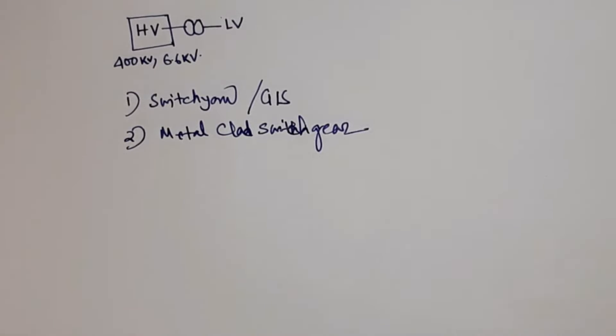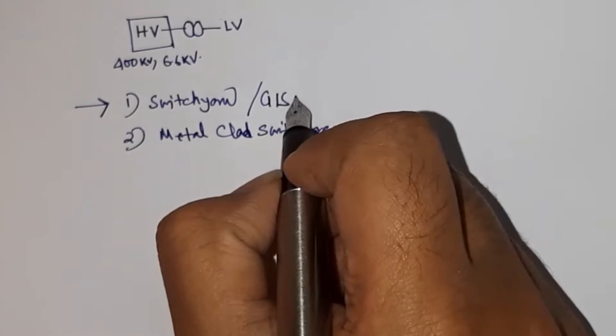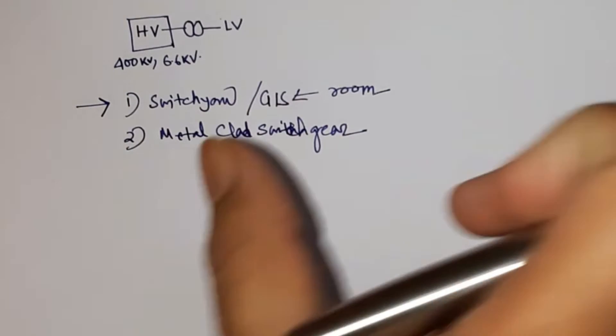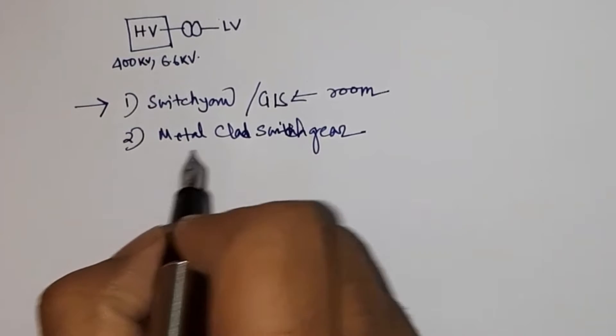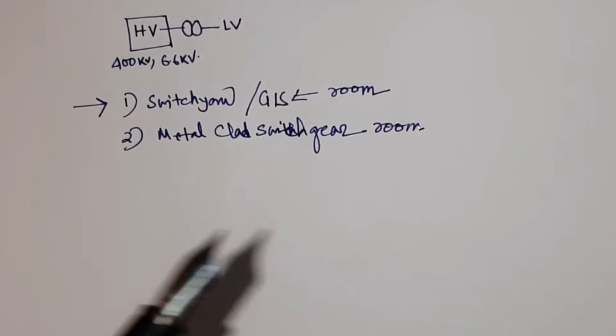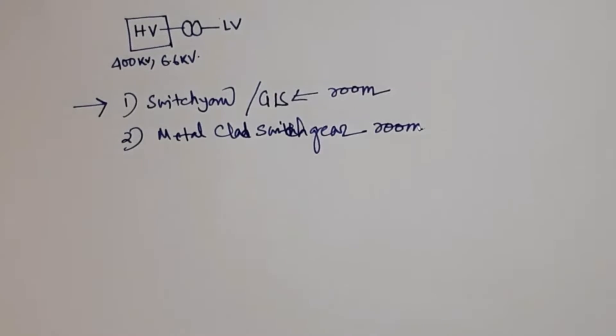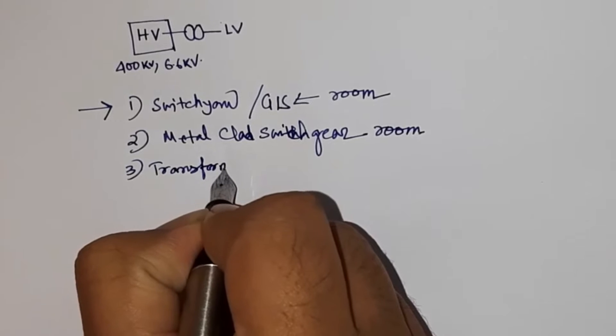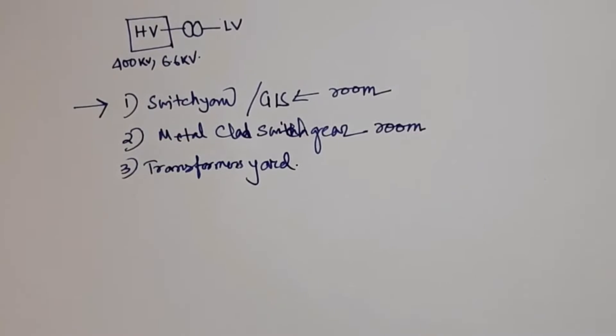So a substation shall consist of the following: if it is outdoor there shall be a switchyard; if it is GIS then there shall be a GIS room. A substation should have a switchyard or GIS if it has an extra high voltage system of 66 kV and above. Then it shall have a metal-clad switchgear room for installation of switchgears, which can be in the range of 3.3 kV, 6.6 kV, 11 kV, 33 kV, or 415 V. Then there shall be a transformer yard where outdoor oil-type transformers will be kept.